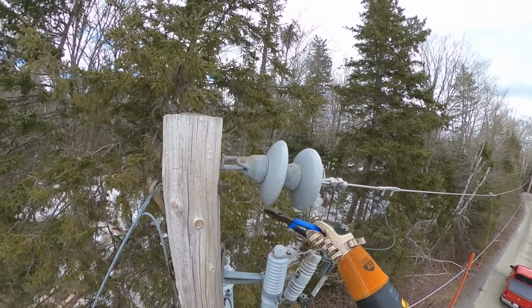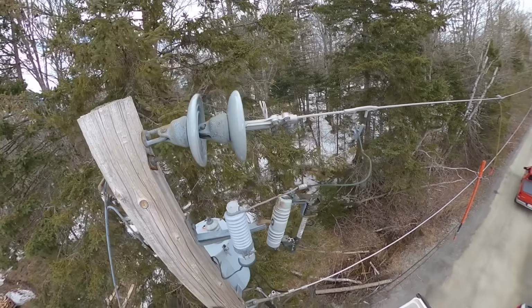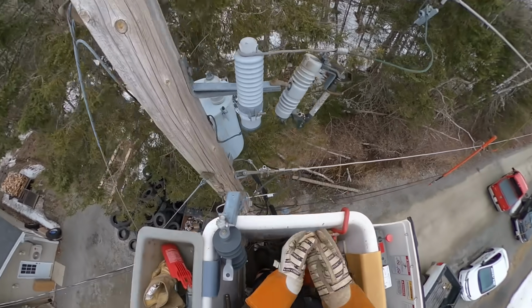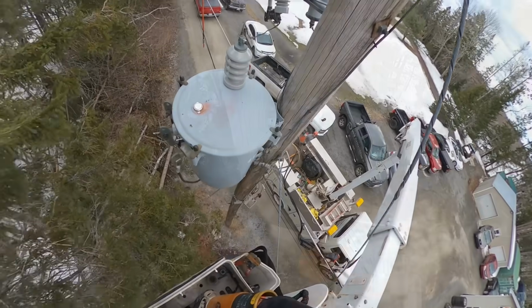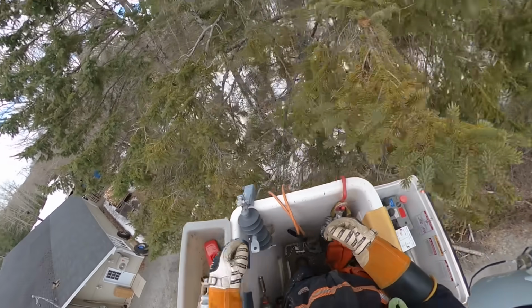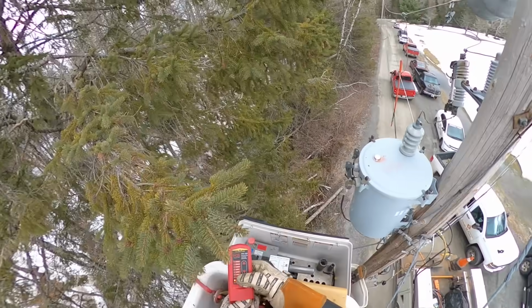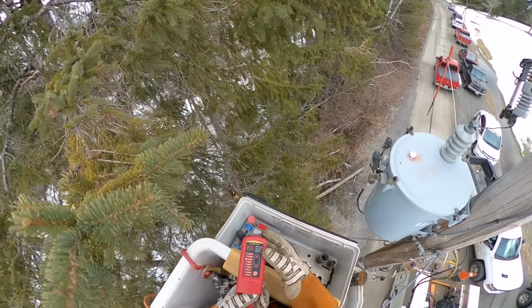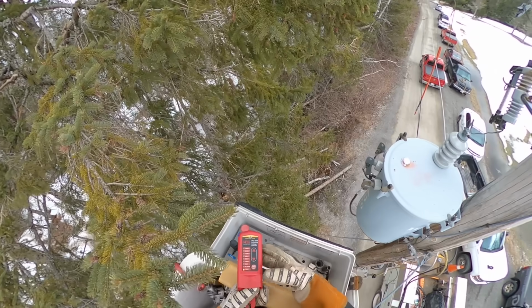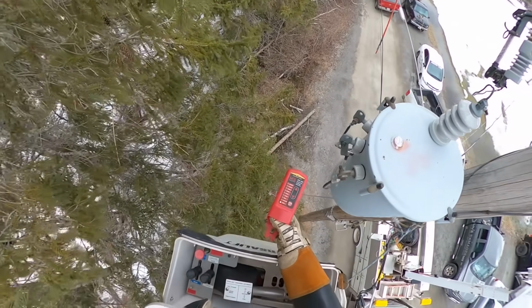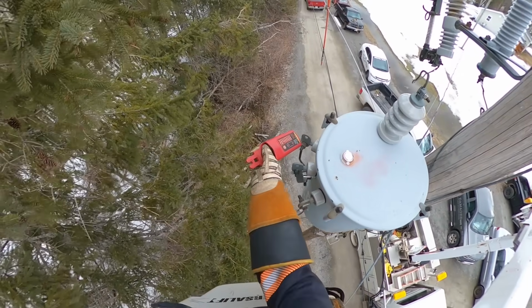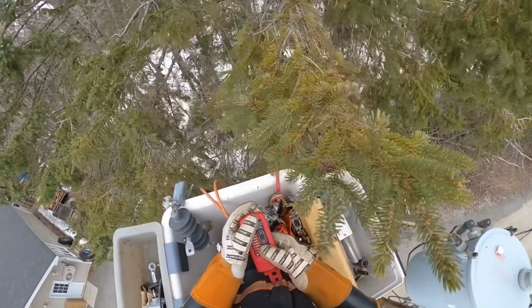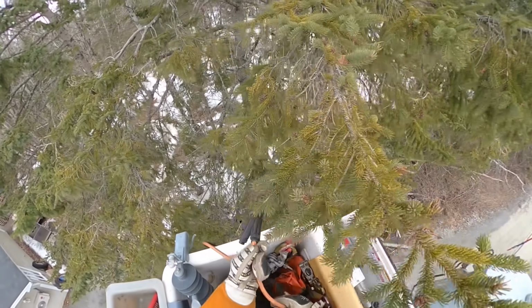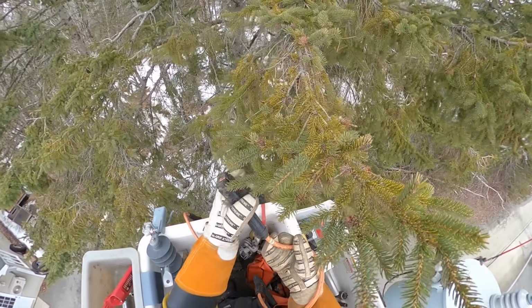You could hear when I was tapping on those insulators, one of them had a dull thud and the other one had a ringing sound. That's just kind of a little check you can do if you're not sure if a bell is broken or not. I'd be awful careful doing it on energized conditions, but sometimes it's hard to see those cracks, so I was just demonstrating how you can find a crack in porcelain if you try to. We call it the ring test. But basically now we're just going to short out the secondary.